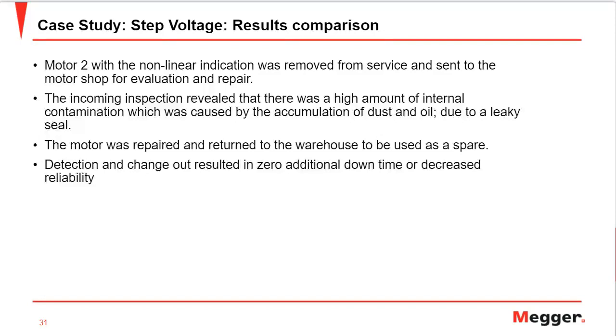What was found is that motor 2 had a high amount of internal contamination, which was caused due to accumulation of dust and oil. So here it was the chemical composition and the mechanical wear and tear. Obviously, once you find there is an issue in the motor, we have some maintenance program. It has to be done to repair the motor, or get it to a motor repair shop to replace the windings. So that was all about the step DC hypot test.